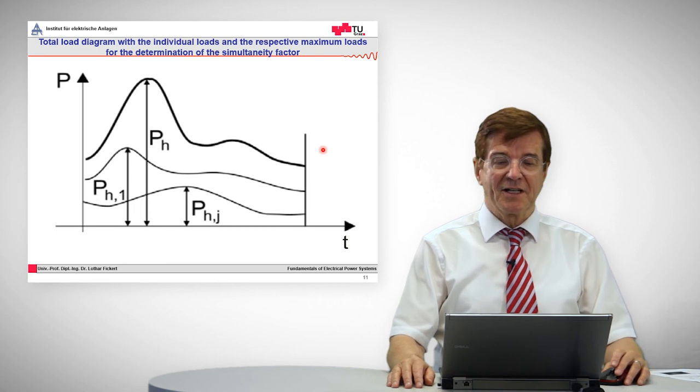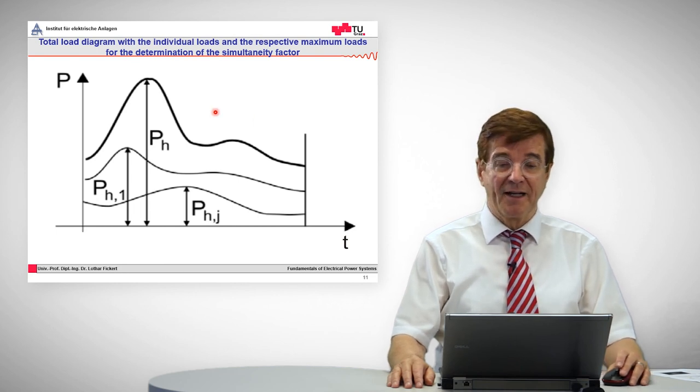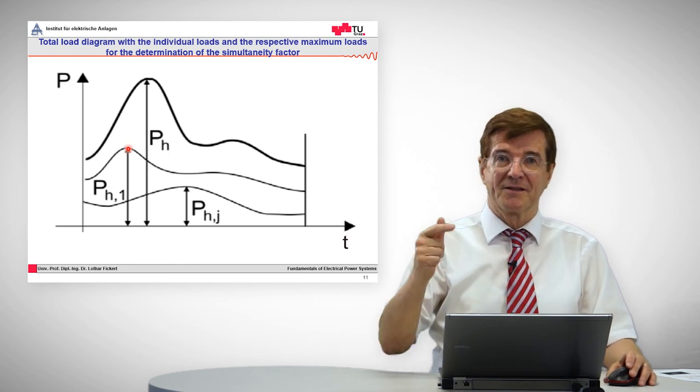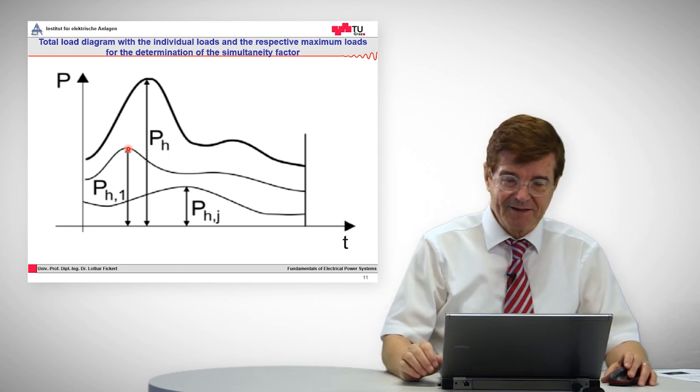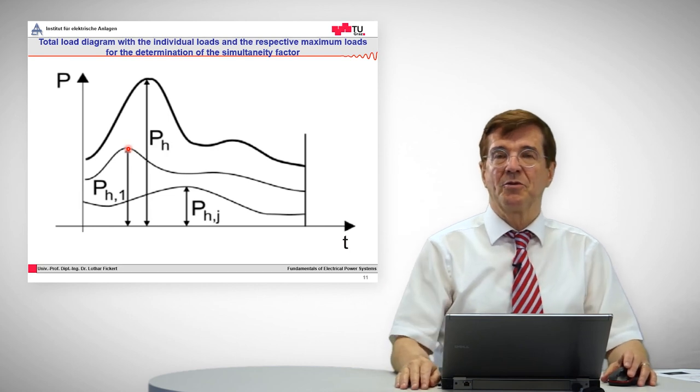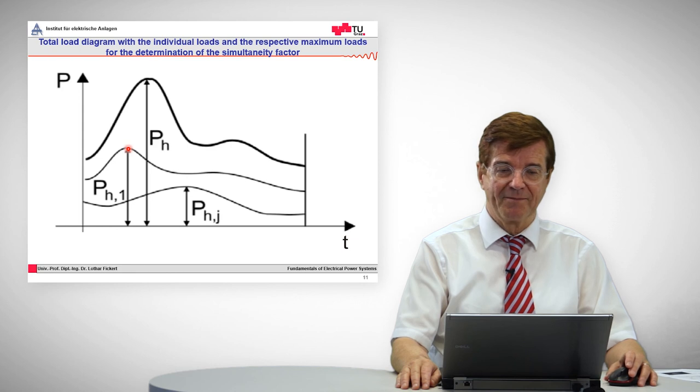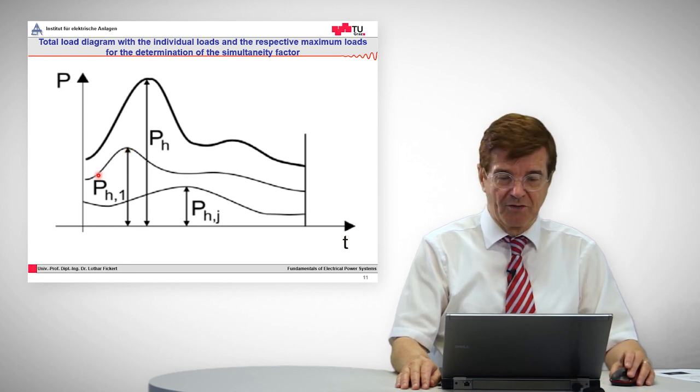When electrical loads are superimposed, and this is important to have the correct rating of all the cables, overhead lines, transformers, then you must determine what is the maximum load that this electrical grid has to supply.